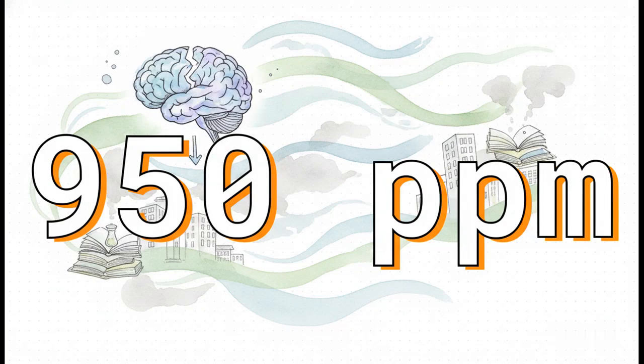Now, I want you to look closely at this number, 950 parts per million. For decades, carbon dioxide was just viewed as a harmless proxy, right? Just a rough indicator of general ventilation. But recent controlled exposure studies, including that research from Harvard, have fundamentally blown that standard out of the water. We now know for a fact that higher-order cognitive function significantly declines at CO2 concentrations as low as 950 ppm. And here's the staggering part. This level is actually incredibly common in indoor spaces. In the past, this would have easily satisfied standard ventilation guidelines.